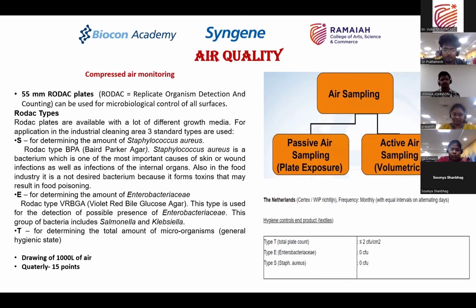Now, how much air will be drawn or taken for this counting? Generally, in case of active sampling, you are going to force some amount of air onto the media. The amount of air used for this counting is 1000 liters. With the help of force, the air will be collected and bombarded on the plates, and then the plates will be incubated and the colony forming units will be counted.